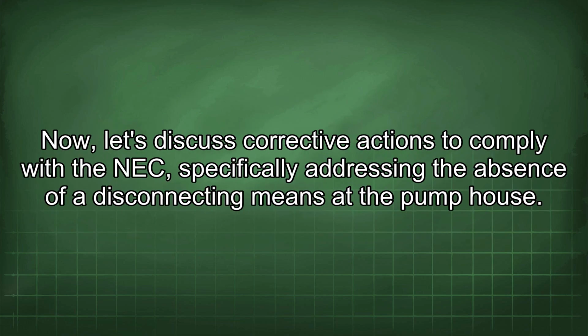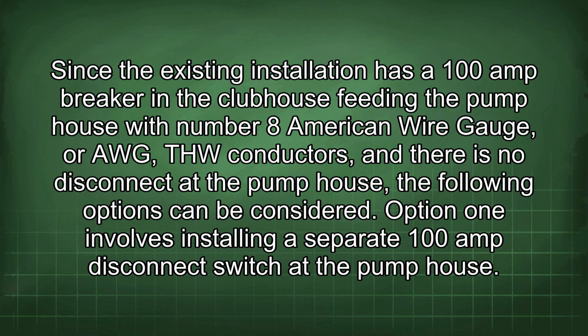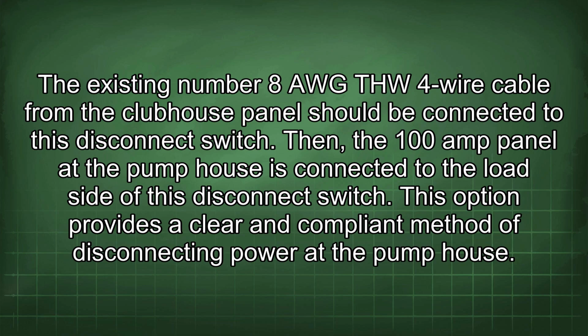Now, let's discuss corrective actions to comply with the NEC, specifically addressing the absence of a disconnecting means at the pump house. Since the existing installation has a 100 amp breaker in the clubhouse feeding the pump house with number 8 American wire gauge, or AWG, THW conductors, and there is no disconnect at the pump house, the following options can be considered. Option 1 involves installing a separate 100 amp disconnect switch at the pump house. The existing number 8 AWG THW 4-wire cable from the clubhouse panel should be connected to this disconnect switch. Then, the 100 amp panel at the pump house is connected to the load side of this disconnect switch. This option provides a clear and compliant method of disconnecting power at the pump house.